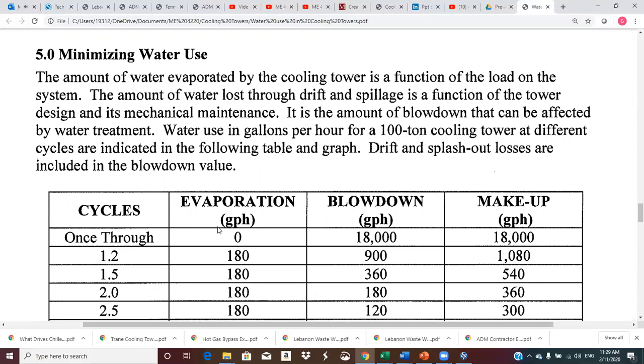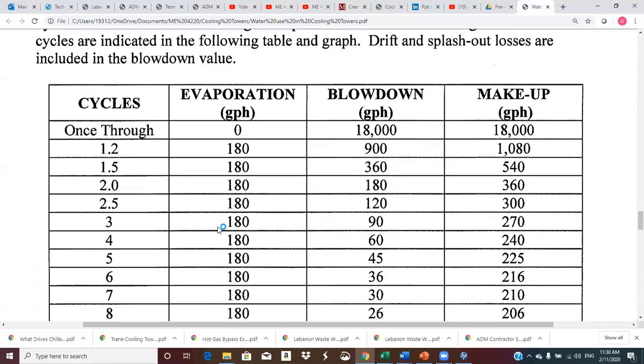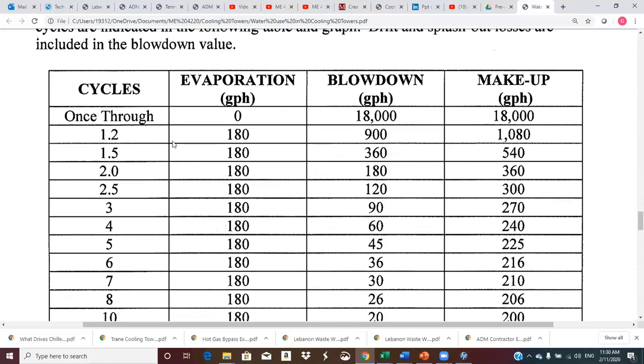Let's see. So water used in gallons per hour for a 100-ton cooling tower at different cycles are shown here. Once through means that we're buying city water, or I guess we could take it out of a creek or whatever, but we're getting water and we just run it through the chiller or the heat exchanger, and then it gets heated up and we throw it back in the creek. So we don't have a cooling tower. It's a once through cooling situation.